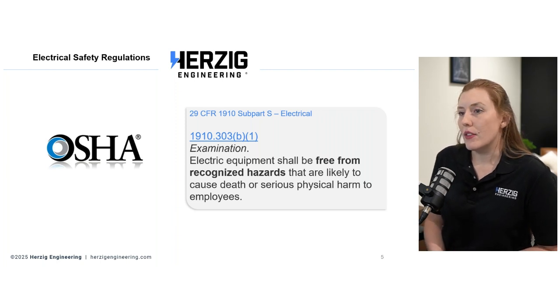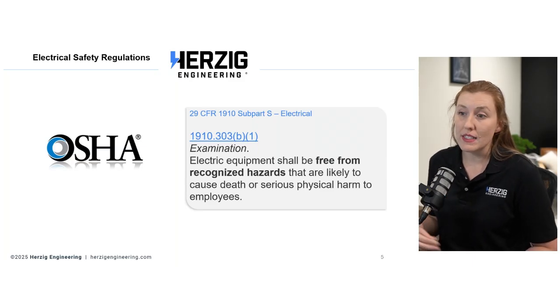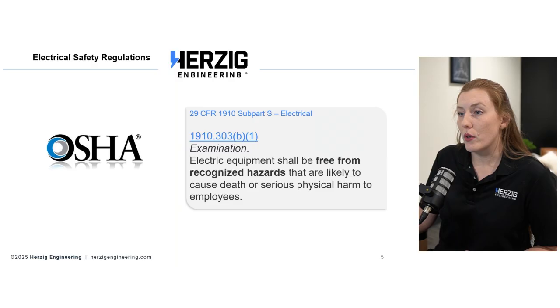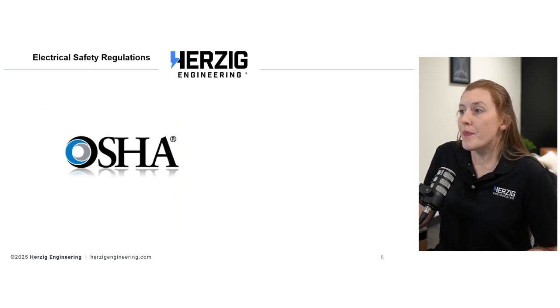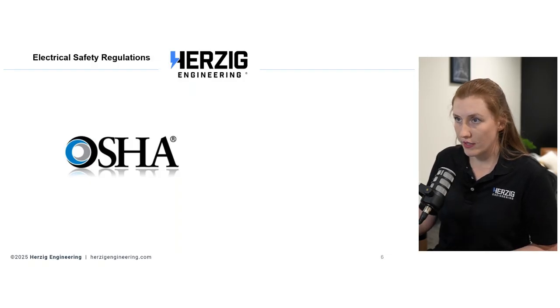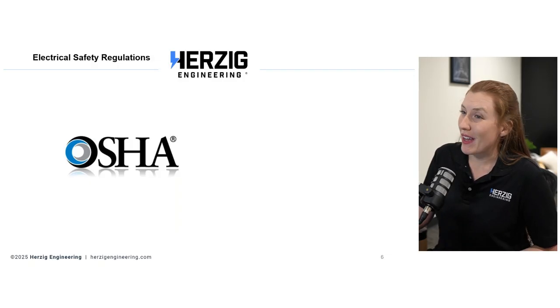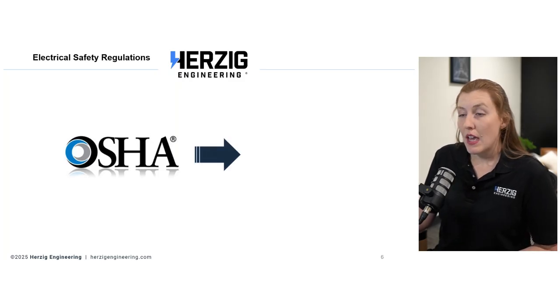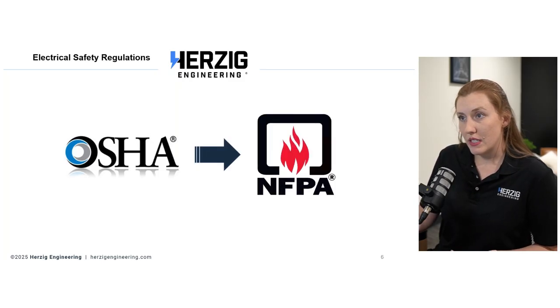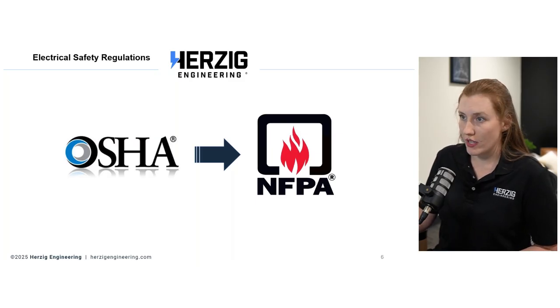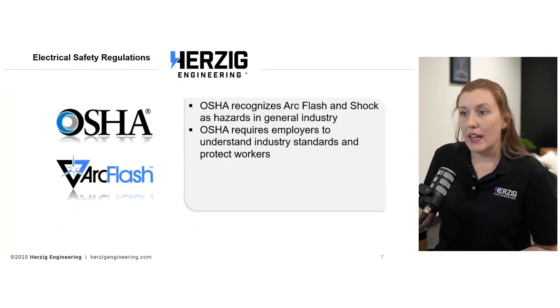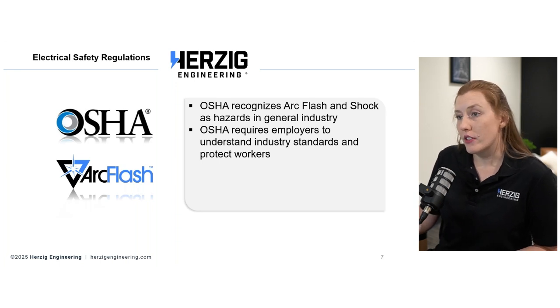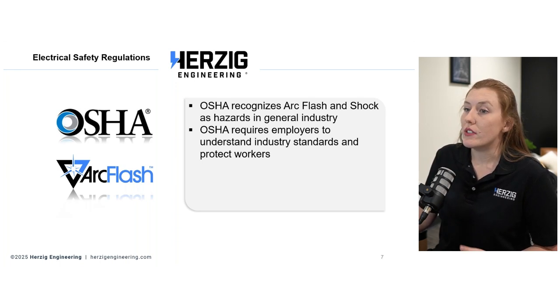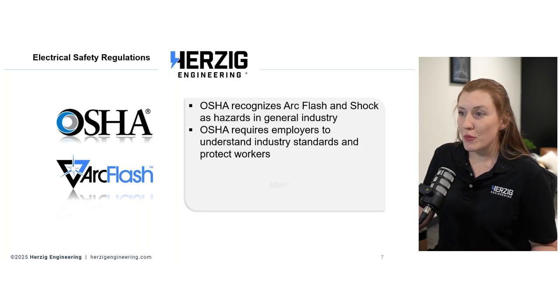Looking at 1910.303, there's a part that talks about needing equipment to be free from recognized hazards that are likely to cause death or serious physical harm to employees. Now, OSHA is set up to tell you what is required - the minimum requirements to keep people out of the hospital or dead, that's the idea. Then you look to the NFPA codes and standards for how to accomplish that. So OSHA recognizes arc flash and electric shock as hazards in general industry and requires employers to understand the industry standards to protect workers.